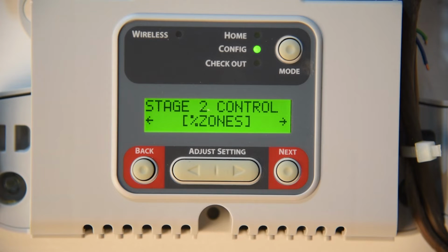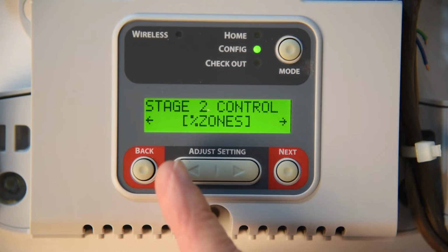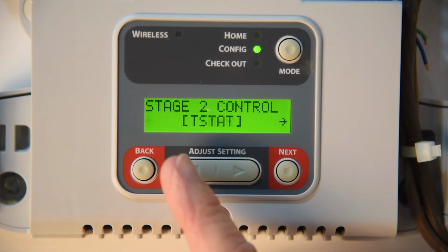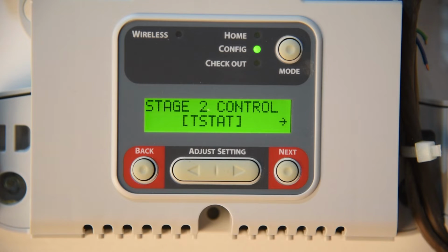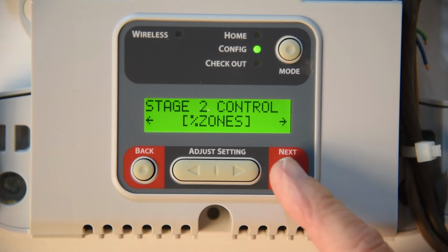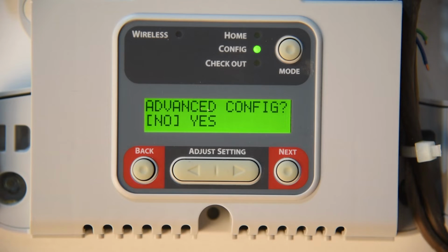Stage 2 control. Well, I only have stage 2 in my heating. I'm going to put it down for percent of zones, but you can have the thermostats control it. If the thermostats are calling for stage 2, then they would control it. There's a timer that can control it. Percentage of zones, and that's it. Or off. I use percentage of zones. So that's next. Advanced configuration. Questions are no and yes. Well, I want to do some advanced configuration on mine. So I hit yes.